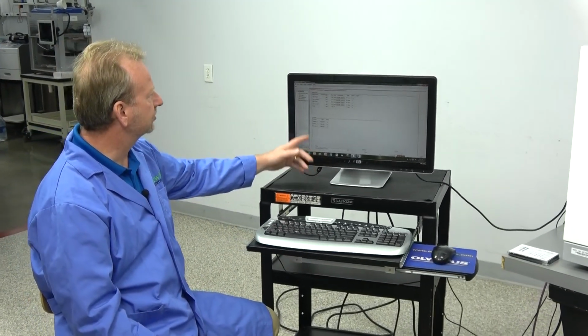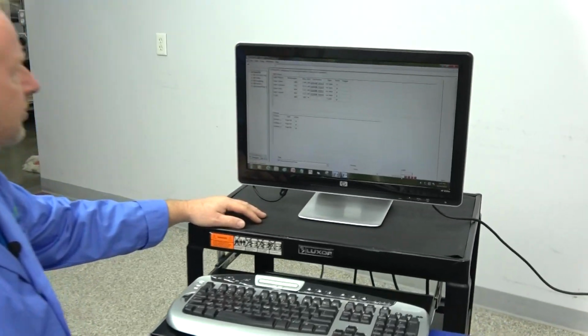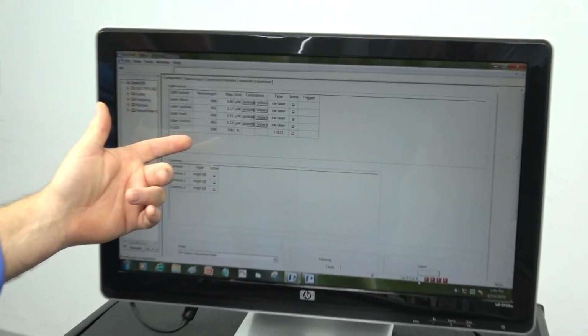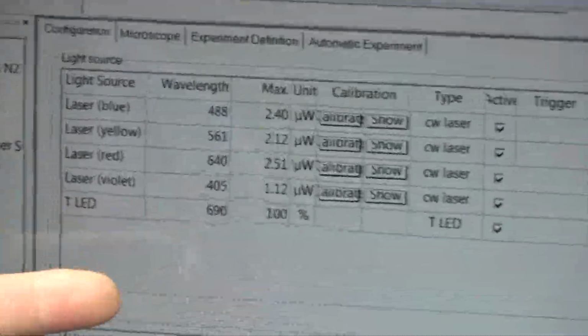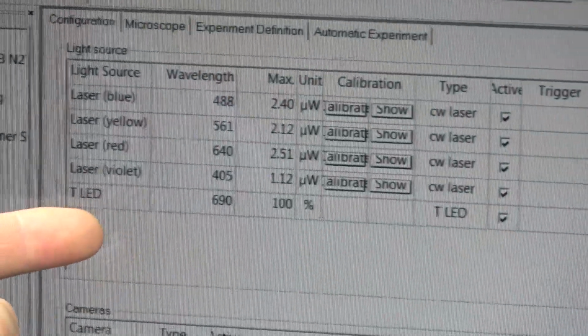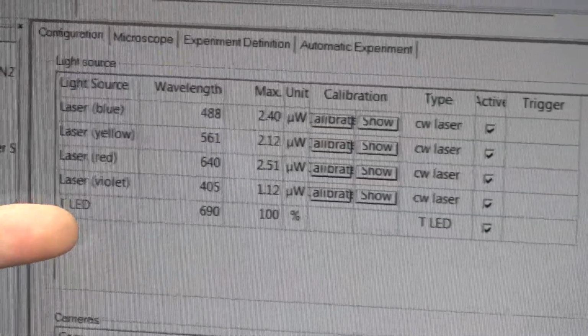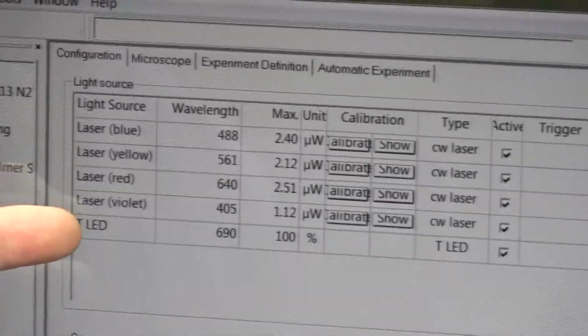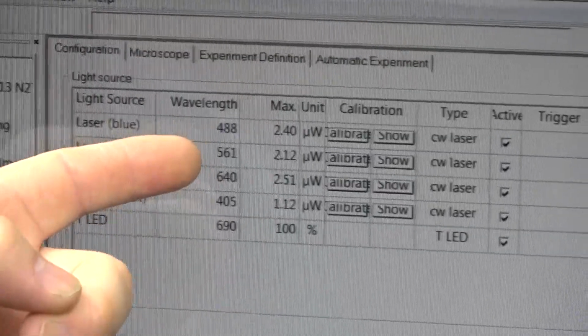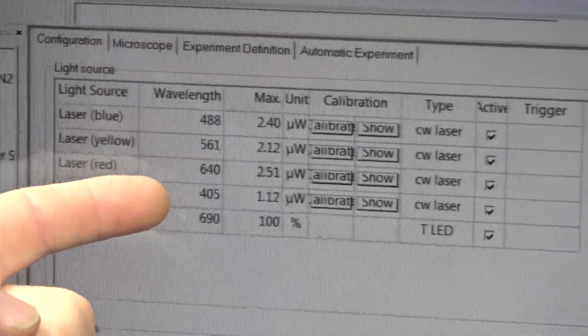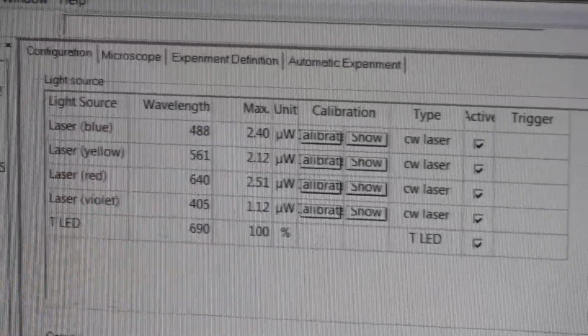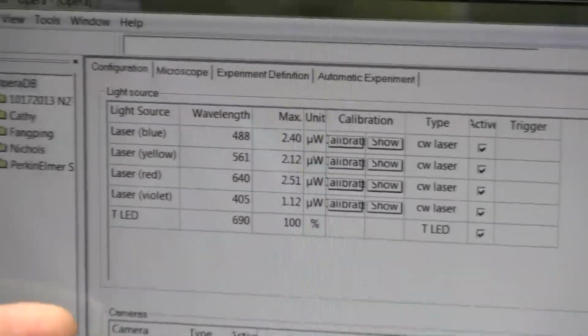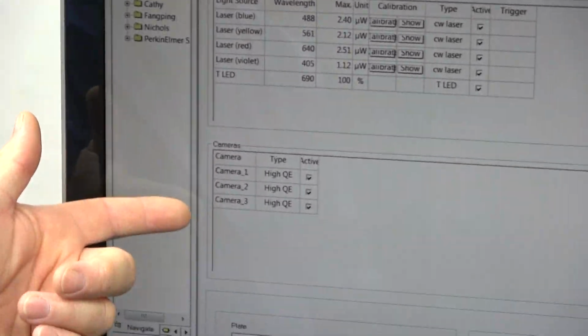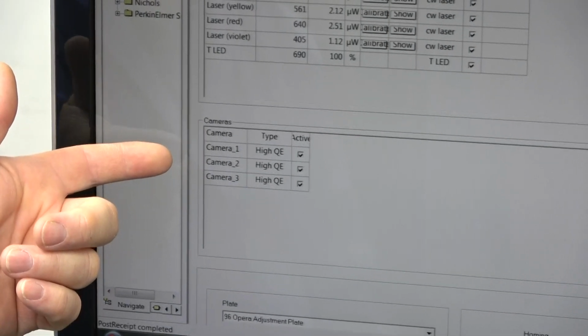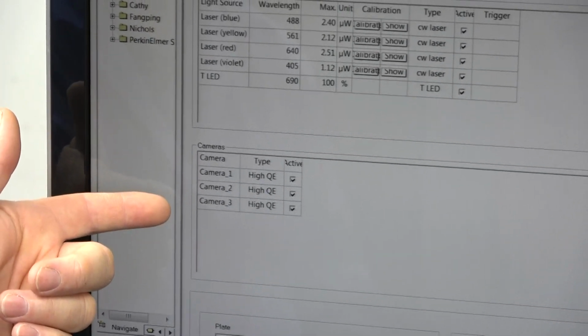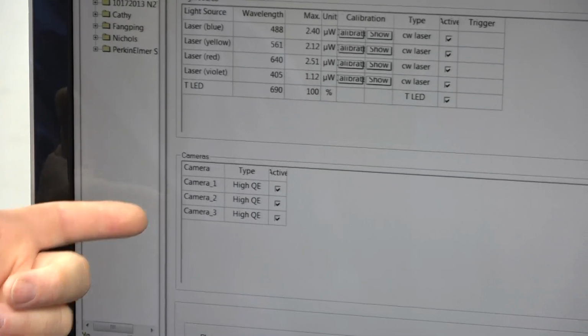Right now we're on the first screen, and the first screen is basically showing all your laser and light sources. This particular unit does not have the UV light source, but it does have the LED down here, you can see. But it does have 4 lasers. It has the 488, the 561, the 640, 405, and of course the LED is a 690. And down here on the cameras, you can see it has 3 cameras, and they're all the CCD high quality cameras, which are air cooled.